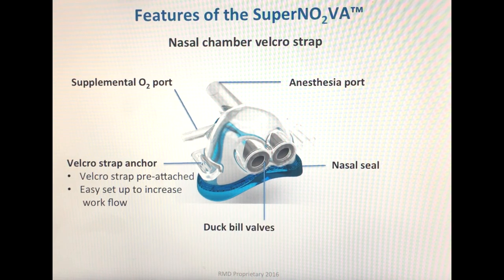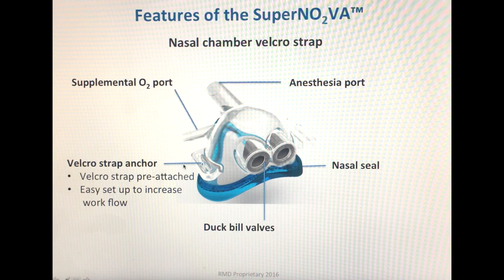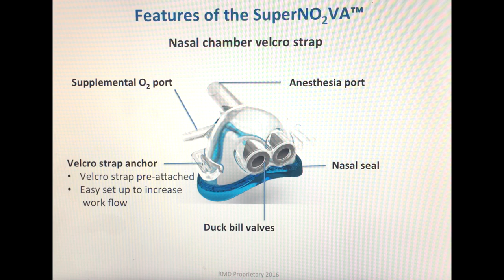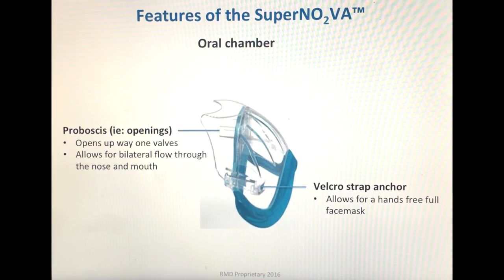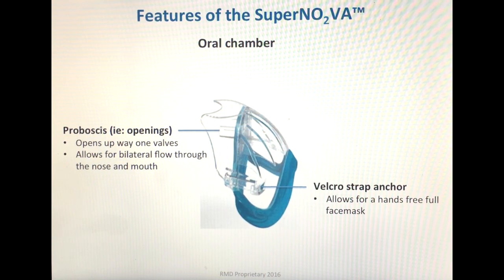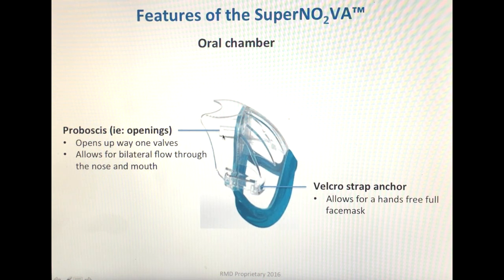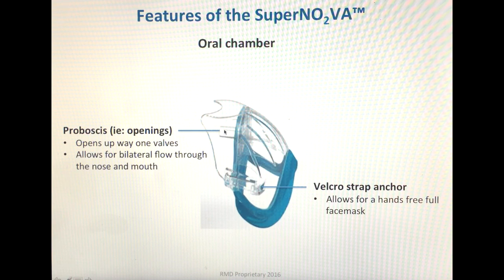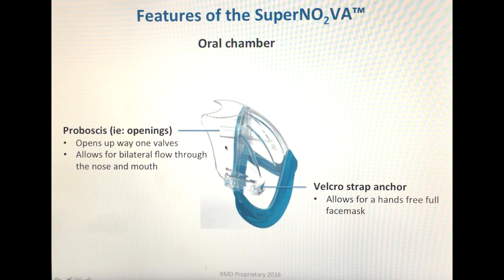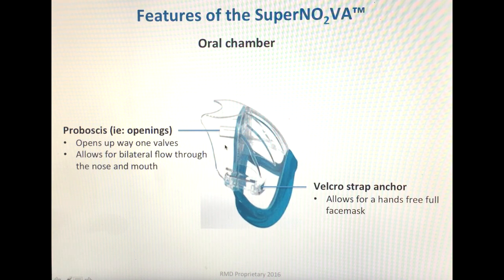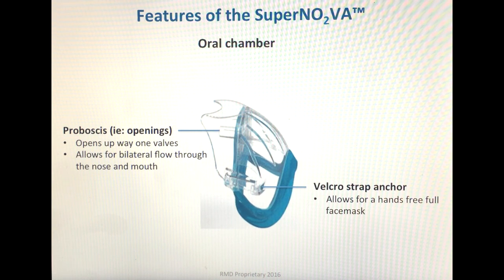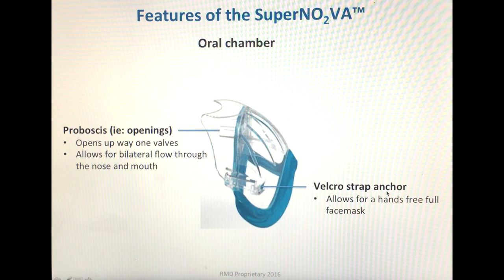A final unique feature of the SuperNO2VA's nasal chamber is the Velcro strap, which helps the clinician increase their workflow by allowing easy access and very quick setup since it comes pre-attached. The SuperNO2VA's first accessory is the oral chamber, which has two proboscis — essentially openings. When the oral chamber is inserted into the nasal chamber, these proboscis open the duckbill valves, allowing for bilateral flow through both the nose and the mouth, essentially acting as a full face mask. The oral chamber also has a Velcro strap, allowing for hands-free full face mask ventilation.